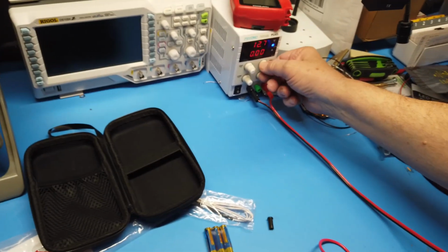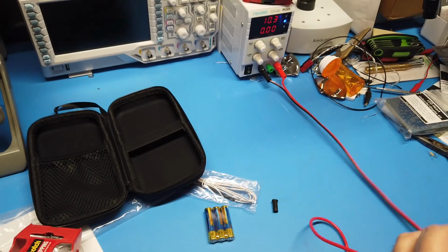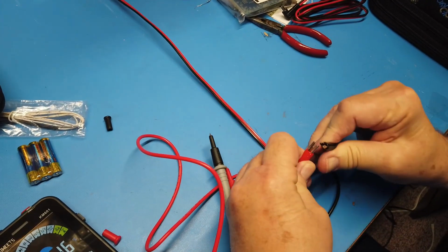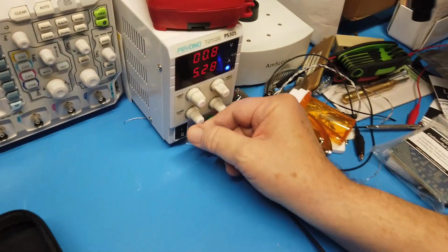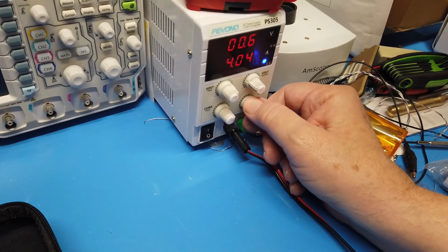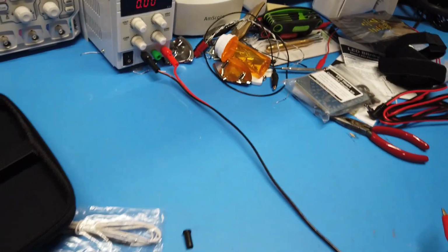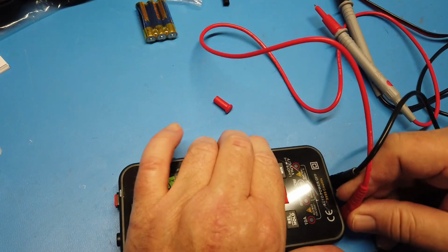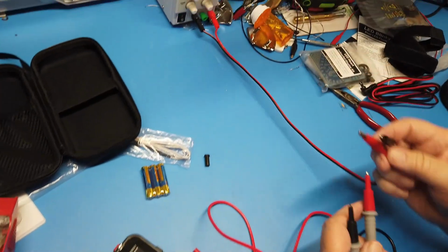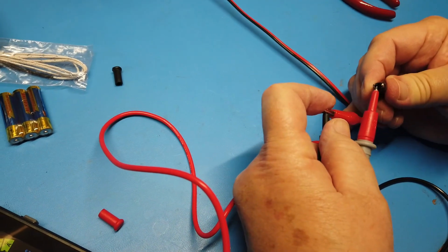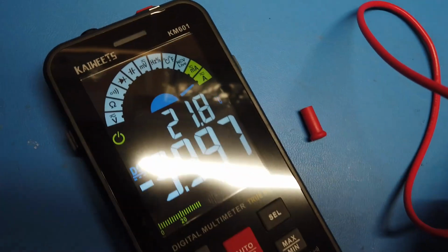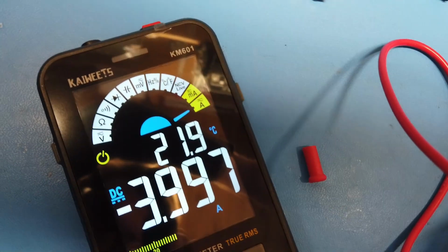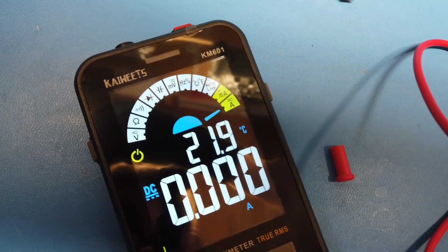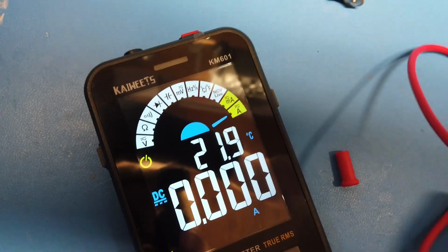Okay, now we're going to turn this and short this thing, and set it up for, let's say, 4 amps. Now we're going to put this over into the 10 amp reading here. This is a current limited supply, so it should tell us the same number of amps as there. 3.997 is the same as 4. Okay, and I've got these backwards, so that's why it's got a minus sign there. So I'm going to put them over like this, as you can see on the camera. And then we've got, well, 4, and again, 22C.